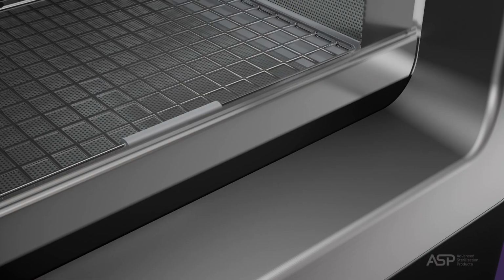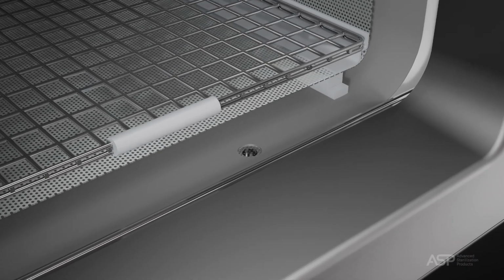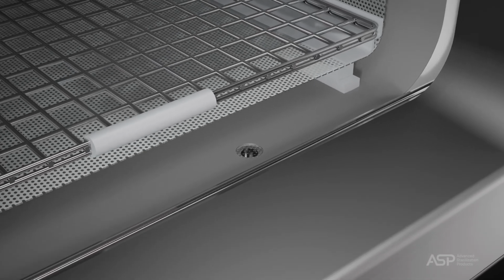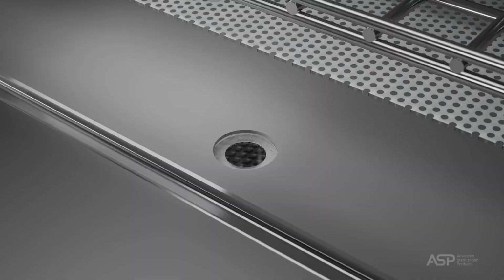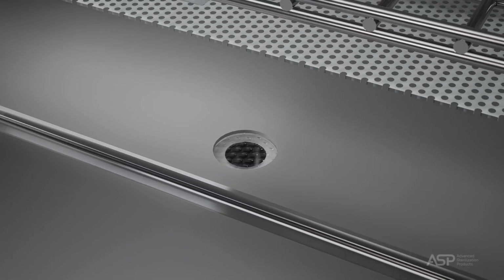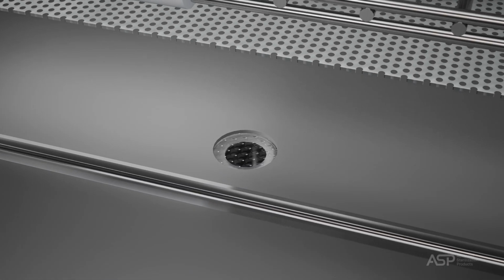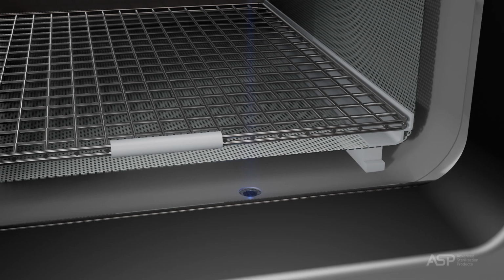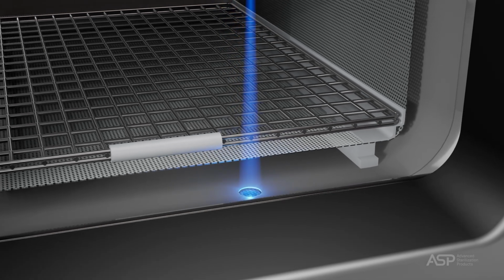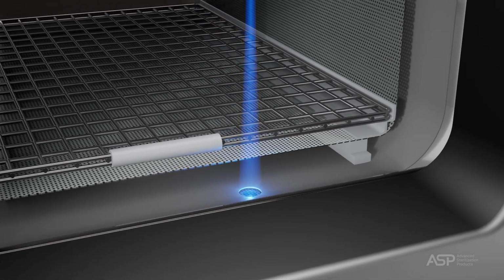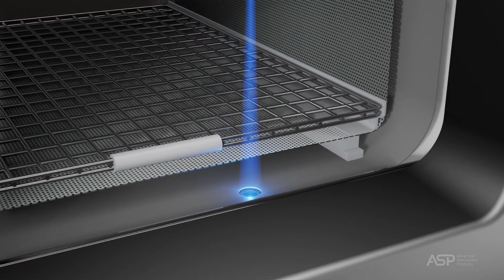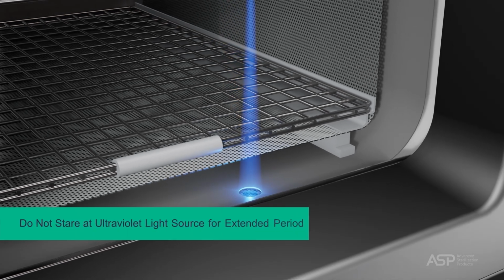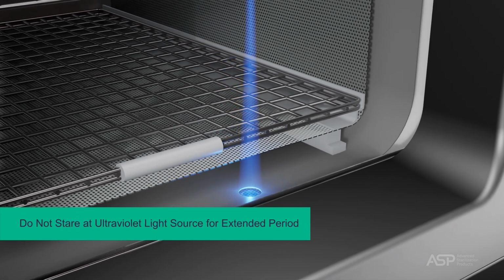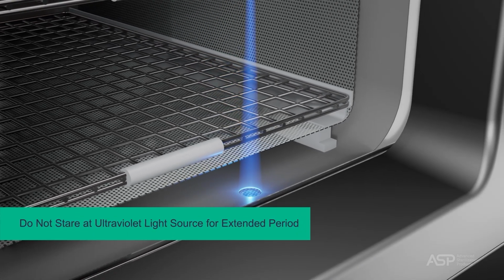Let's talk about maintenance. The hydrogen peroxide monitor lens is located inside the opening and must be kept clean. Clean the lens once every 3 months or when an accumulation of debris is present. Be advised that the hydrogen peroxide monitor uses an ultraviolet light source located inside the chamber behind the door. To avoid eye injury, do not stare directly at the ultraviolet light source for an extended period of time.